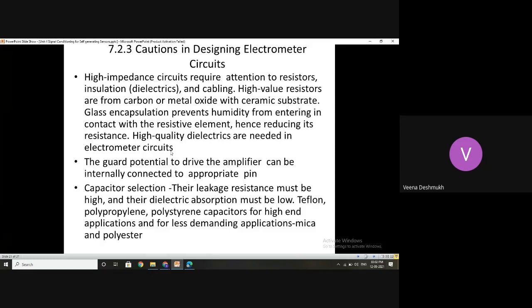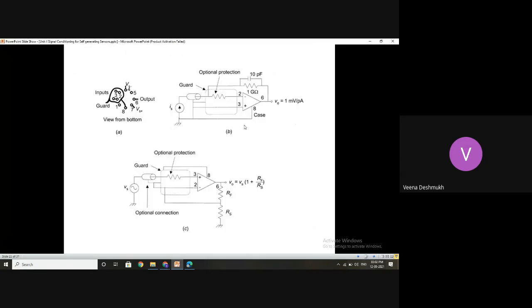To maintain these reference voltages at appropriate levels, proper connections are to be made with the amplifiers which are used. The guard potential to drive the amplifier can be internally connected to the appropriate pin. Here in the circuit, you can see these are the guards, connected to this potential. There is a case, there is a guard. All of them are maintained. You can see here, the case is connected to ground and the same casing potential is connected to this guard. Also, there is a block here that is also a guard. They have to be maintained properly.